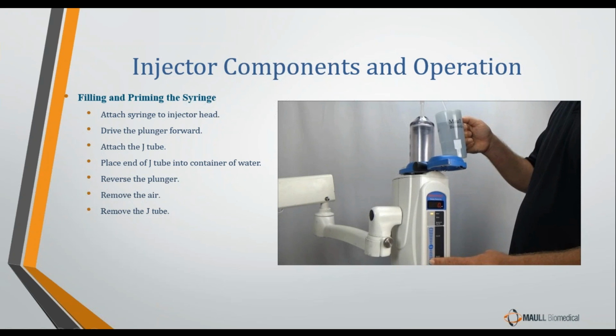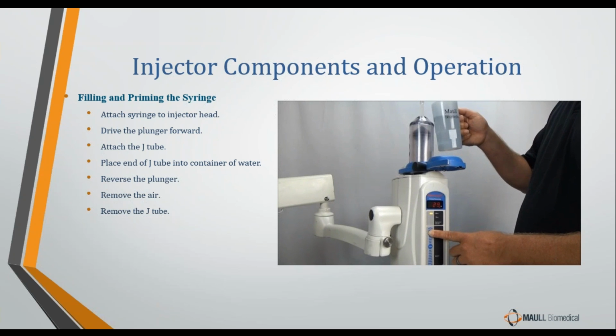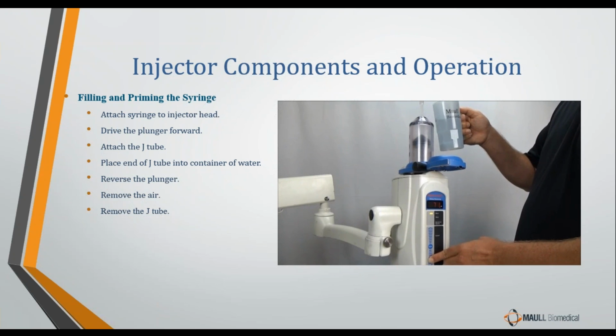Once the syringe is attached, we're going to typically put the end of the J-tube into your container of water. They'll obviously need contrast, but for maintenance purposes, you just use water. We use the forward and reverse load buttons to fill the syringe with as much contrast or fluid as we need while getting out all the air that we can. Then we drive the plunger backwards to fill it up with as much fluid as we need. I think here we're going to 100 milliliters.